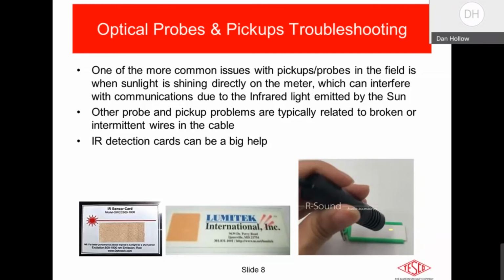And that sunlight can just totally saturate the phototransistor in the meter. And a lot of meter manufacturers have gone to many lengths and done things to prevent this problem, the ambient light from the sun getting in there, because the sun does contain infrared light. And if that infrared light saturates that phototransistor, you are not going to be able to communicate with that meter. So a lot of times I've seen people take a notebook, their hat, many other things, and put it over the meter to shade the meter so the sunlight's not coming in on that optical port. But that is a big problem.